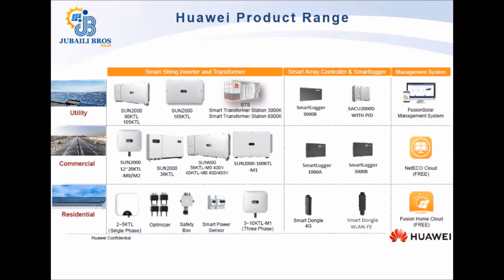The next inverter model is the SUN2000 36KTL, followed by the 50, 60 and the 100 kTL inverters. These are all low voltage inverters. The utility scale inverters are all with 800 volt output, which requires termination of the PV system in the MV cabinet. At the bottom, you can see the residential inverters.